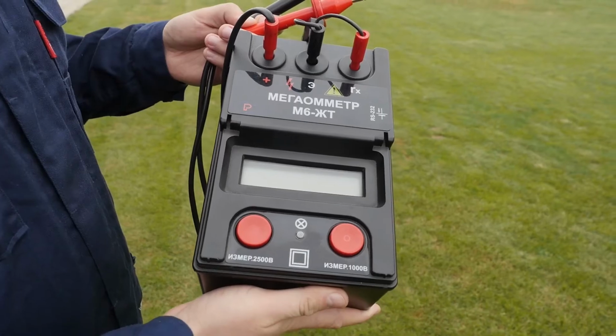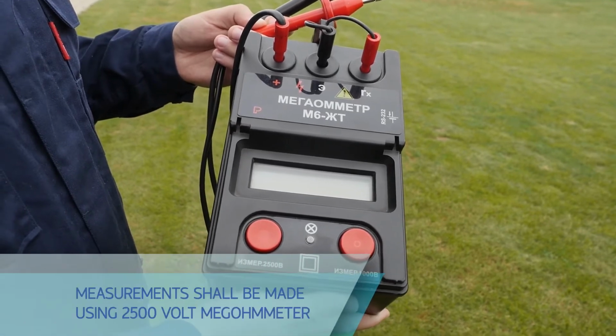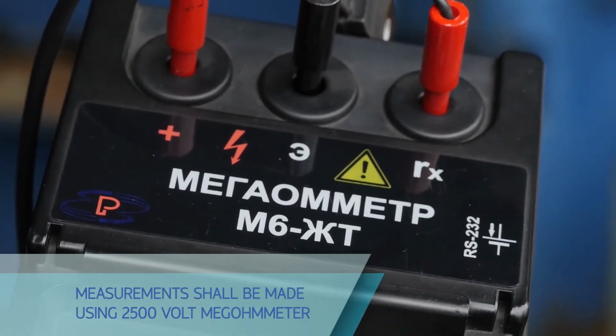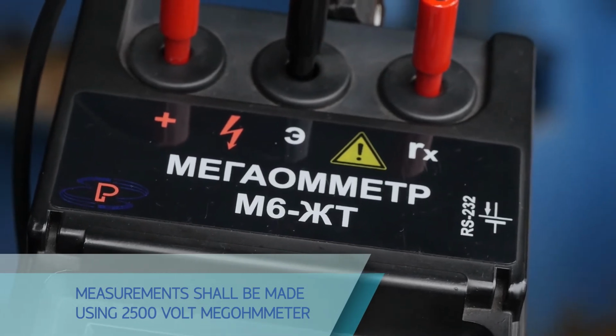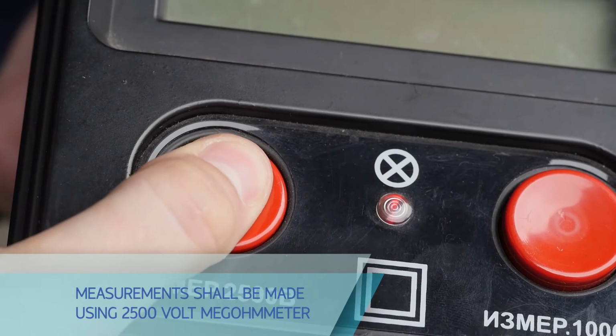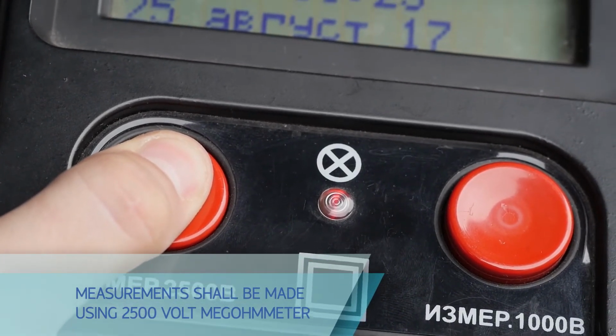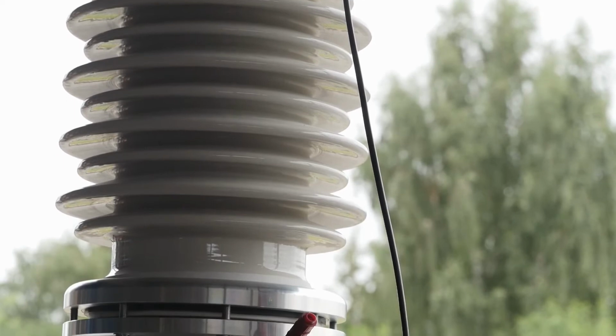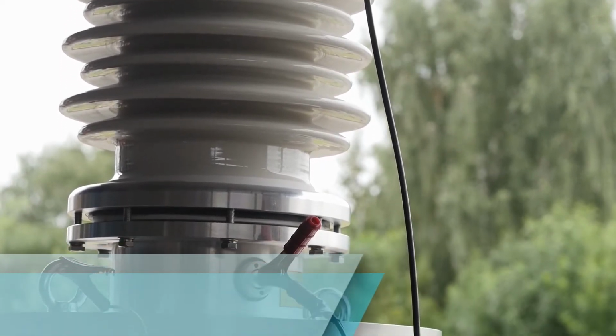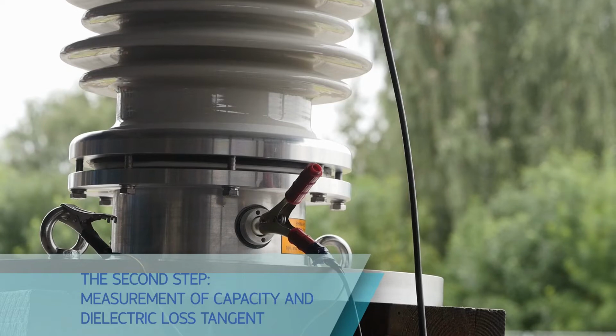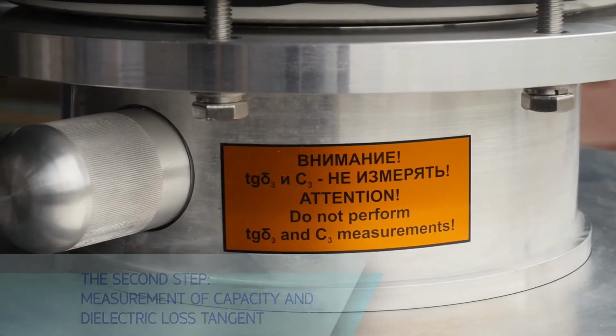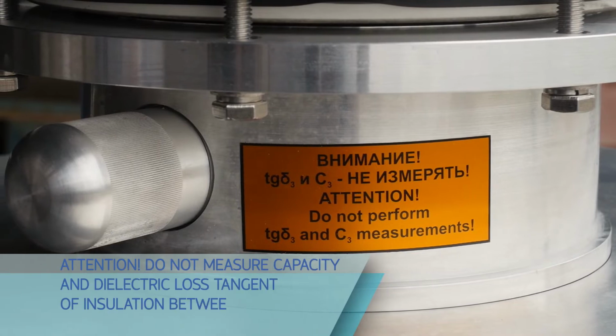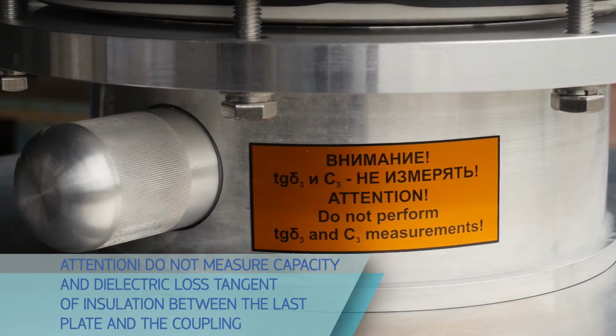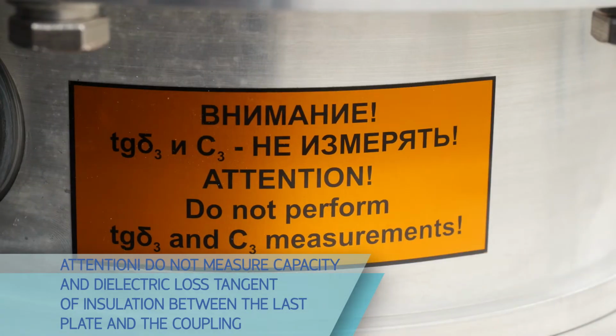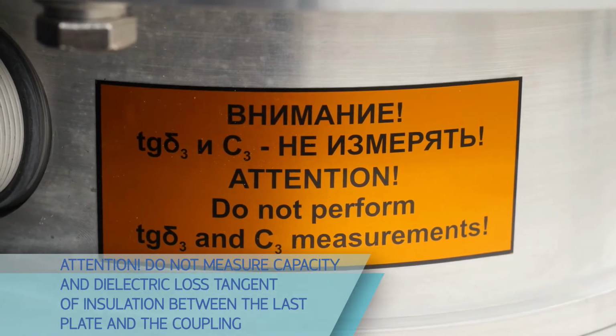Measure the test tap insulation resistance using a 2500 volt megohmmeter. The final value of the insulation resistance, continuity, shall be 1000 meg-ohm minimum during commissioning and 500 meg-ohm minimum during operation. The second step, measurement of capacity and dielectric loss tangent of the main bushing insulation. Attention! Do not measure capacity and dielectric loss tangent of insulation between the last plate and the coupling, since the voltage applied may damage the test tap unit electrically.